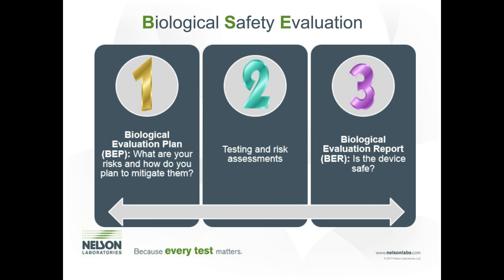And then once that plan is developed and goes through all that risk evaluation, then we move into what is needed to mitigate that risk. It is possible, although it is hard to do, to meet all the risks in that initial plan with some justifications. But most of the time, we don't have sufficient information about the materials and processing of a medical device to mitigate all the risks that that medical device poses. So we do have to fill in gaps from that initial plan with testing and assessments.